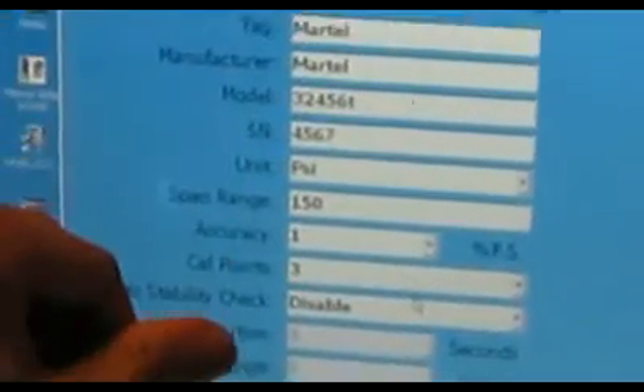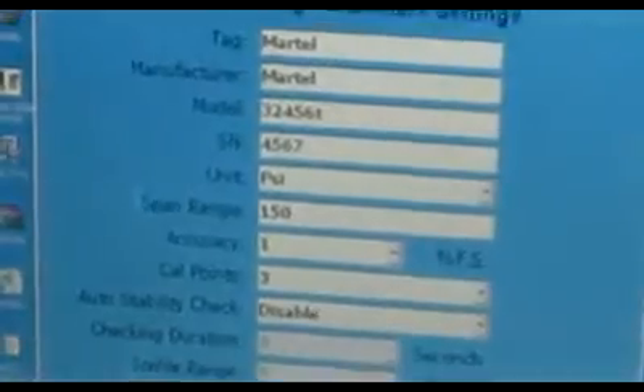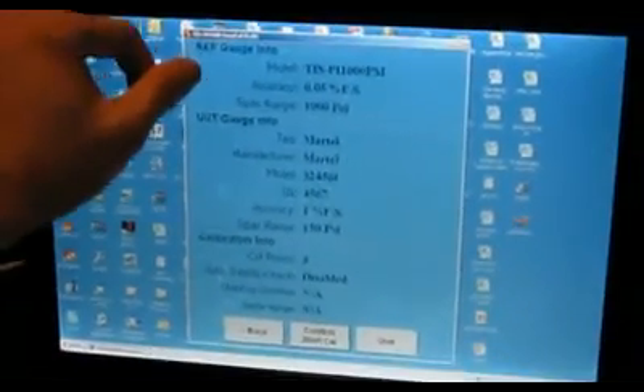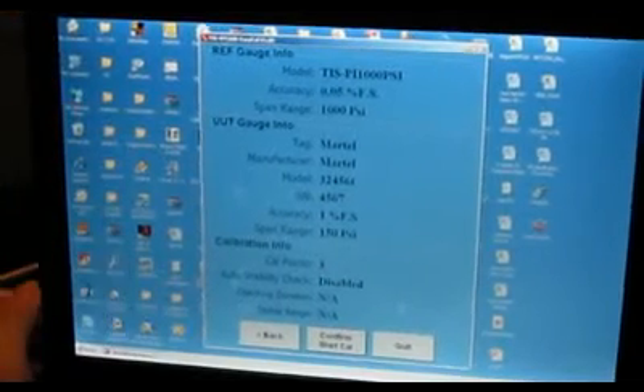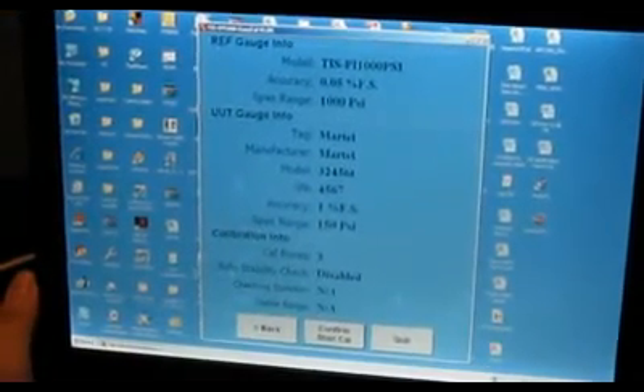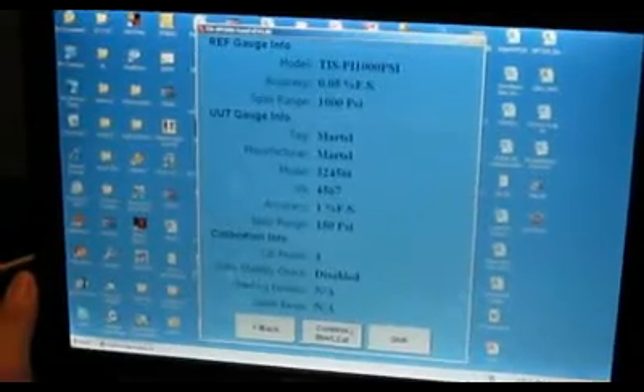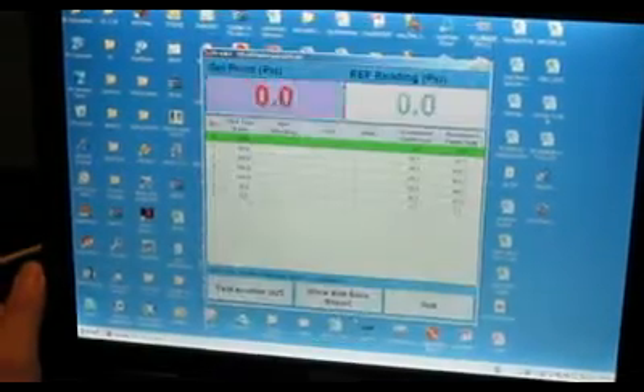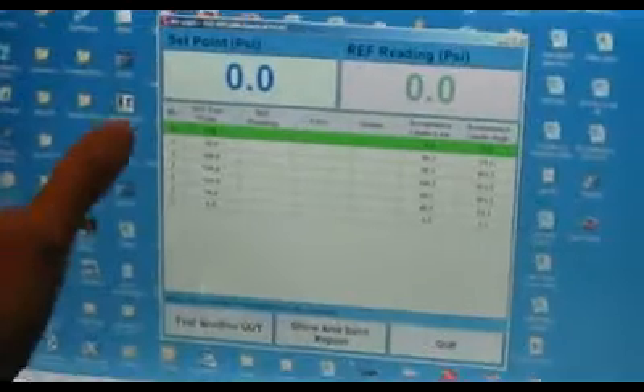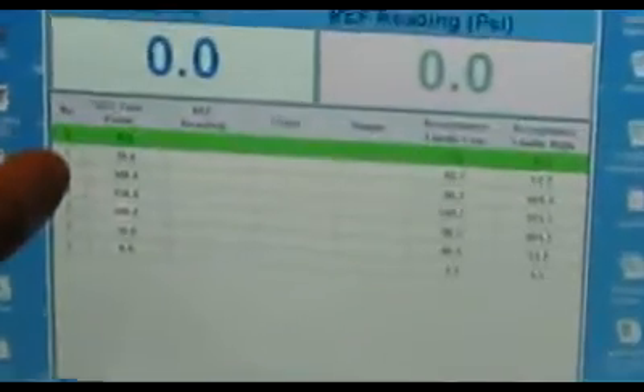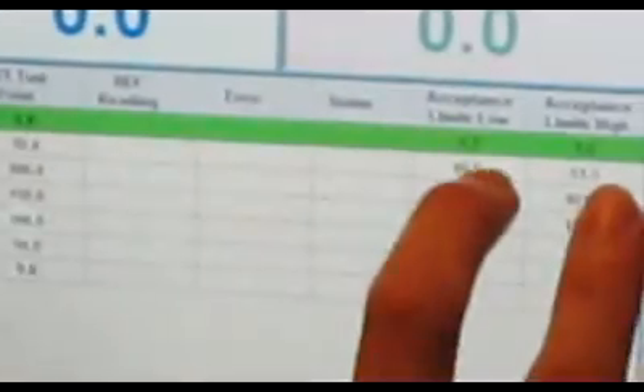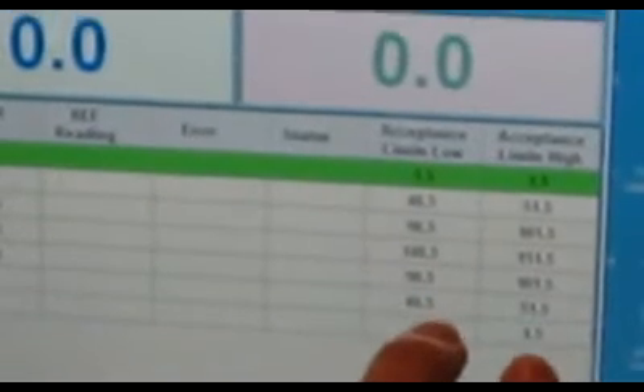After all this information has been keyed in, we simply click on Next. Next, we are able to verify all the data that will be presented in the Excel or in the PDF in a short while. Next, we are able to show all the cal points 0, 50, 100, 150, then the descendings. The acceptance limits are automatically calculated based on 1% of the full span of 150 psi.